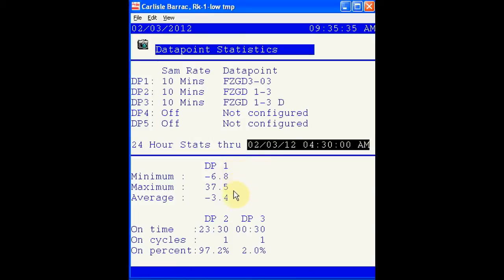We can tell based on the screen that data point number 1 is the temperature for frozen food glass door 3-03. And it's important to note that in the last 24 hours through 4:30 a.m. today, the minimum temperature was -6.8, the max temp was 37.5, and the average temp in that time frame was -3.4 degrees Fahrenheit.